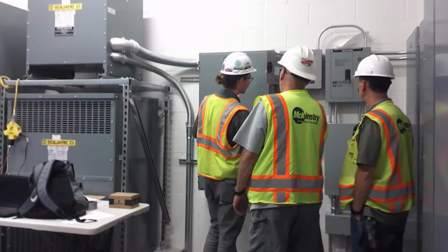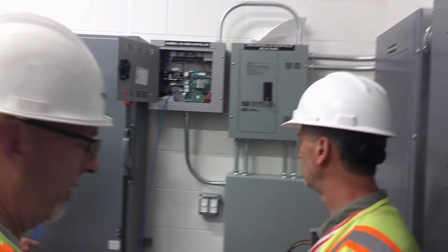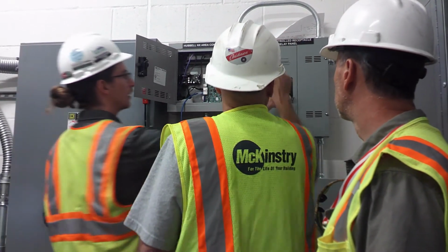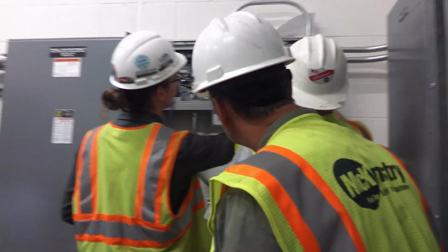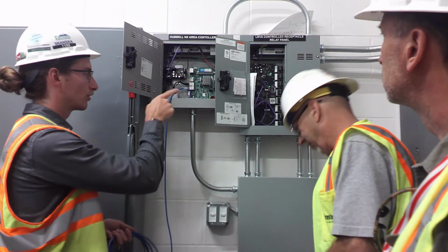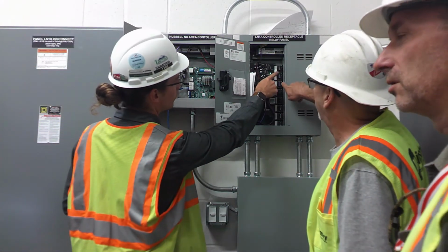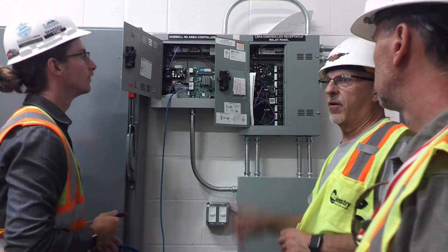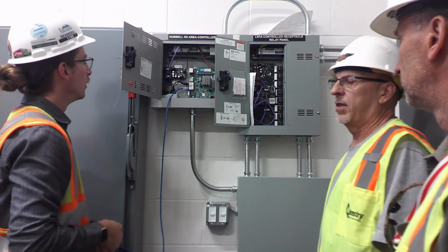So you'll, bypass switches? Yeah, those are going to be exterior overhead switches. Nice. Yeah, that's something I wish they would have done over at the district office. We had to do some stuff through this, and then there's another cabinet that's like this but bigger. And there was an override button we figured out we had to press. Yep, these little guys. Yeah, that one. So, I guess I didn't mention that. That's something good to know. You can manually switch the relays just through that button. Like for the parking lot lights, we had to do it because there were two of them that were burnt out, and the contractor was there, and that's how we did it. We didn't have these over at district office.